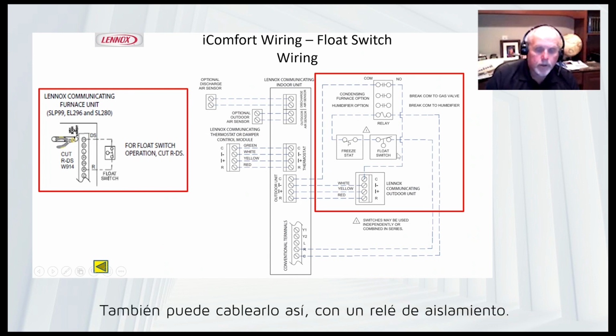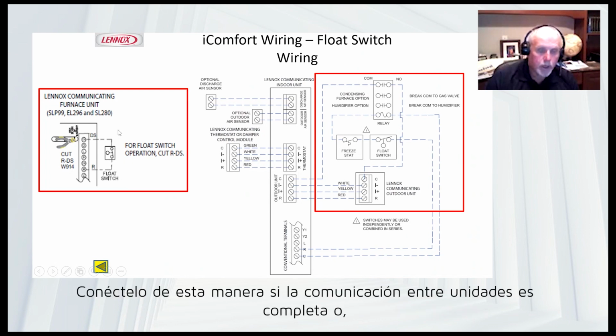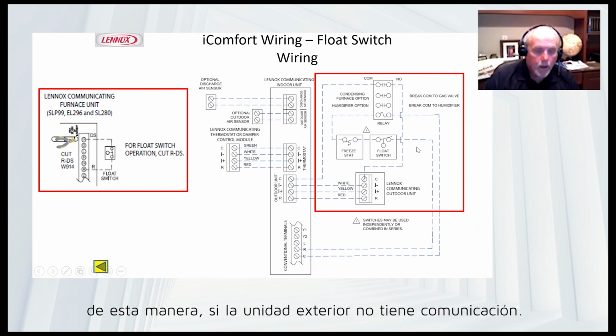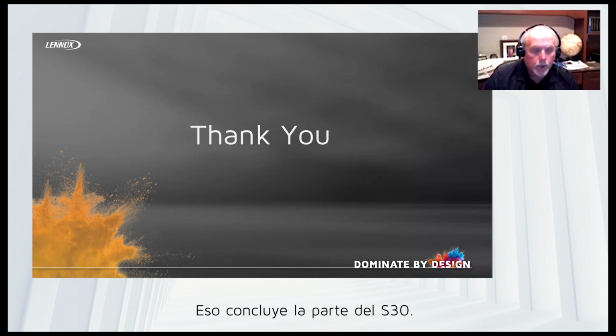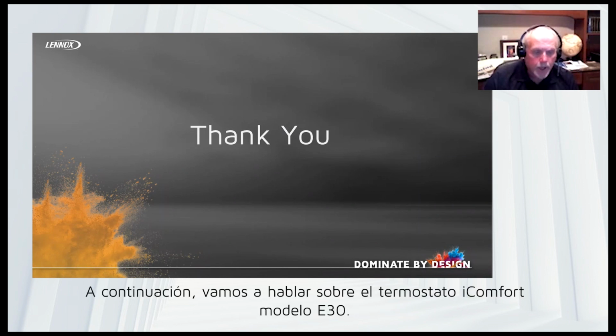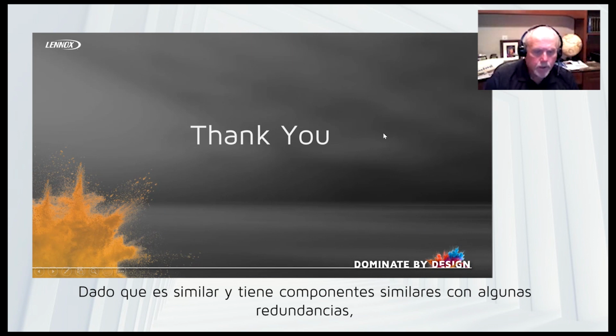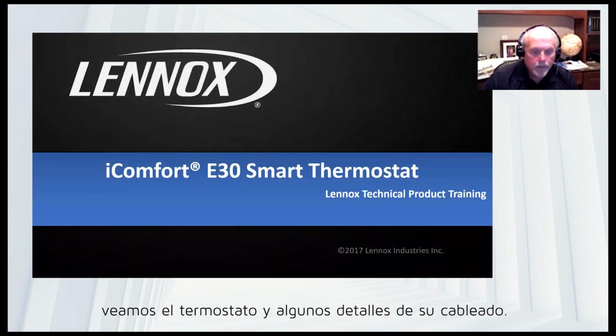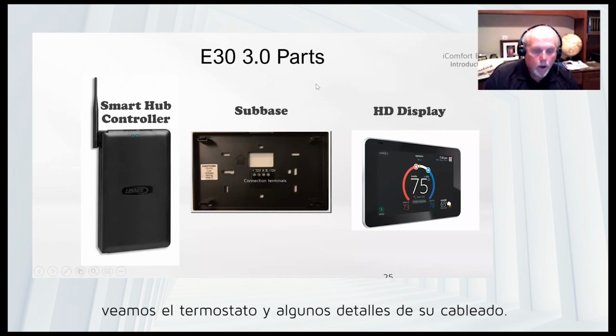Okay. You can also wire it like this, with an isolation relay. Never put a float switch just in line. Either wire it like this if it's fully communicating, or if you have a non-communicating outdoor unit. Okay, so that concludes the S30. So we're going to go ahead and look at the E30 here, since it is similar and has similar components, a couple of redundant components. And so we're just going to look at the E30 thermostat, and we'll look at some of its wiring.